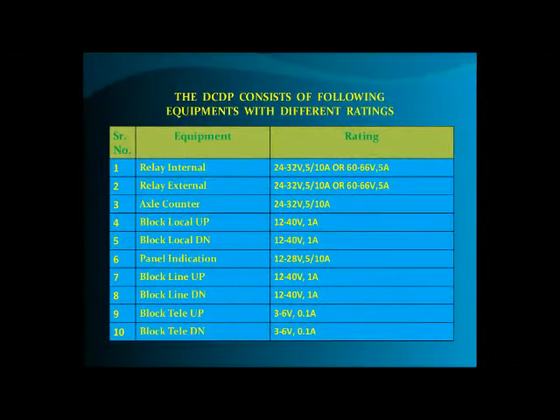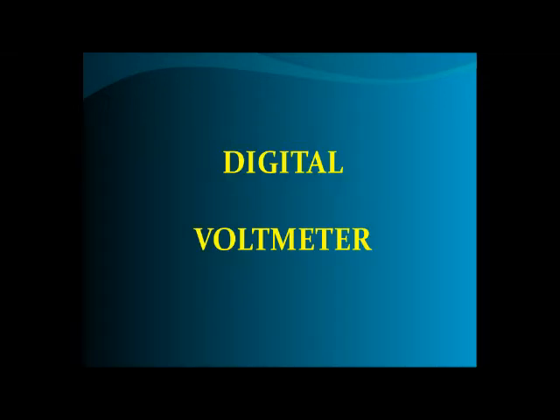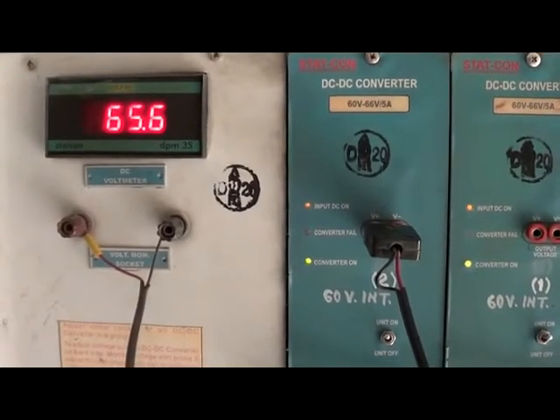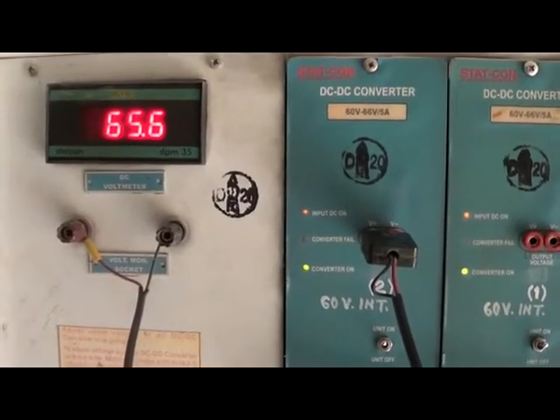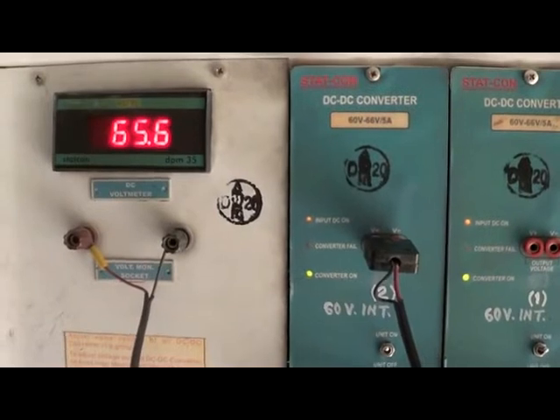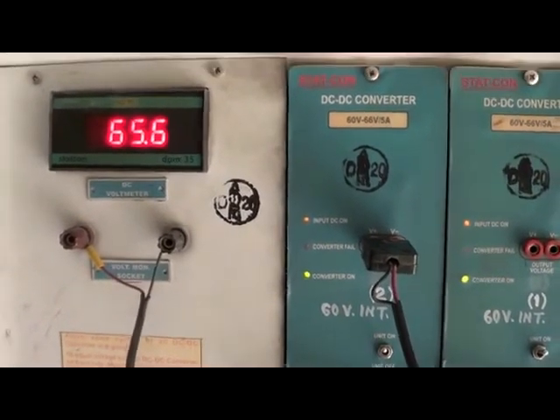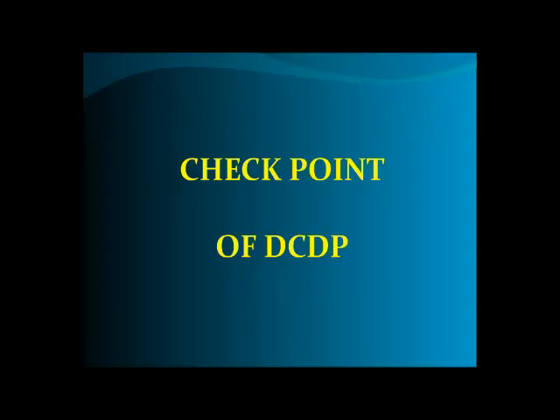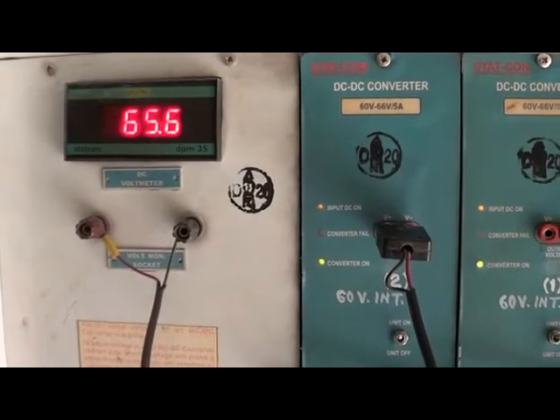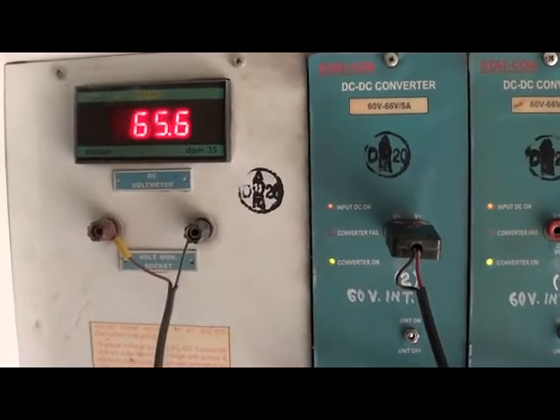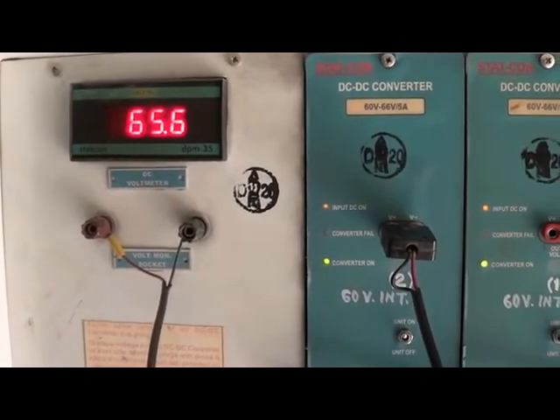The DC Distribution Panel (DCDP) consists of equipment with different ratings. A 3.5-digit LCD or LED display digital voltmeter with extendable cords is provided on the front panel for measurement of output voltages of DC-DC converters. Check points for DCDP: check output voltage of each DC-DC converter on the DCDP common digital voltmeter. Periodicity: once in 15 days.